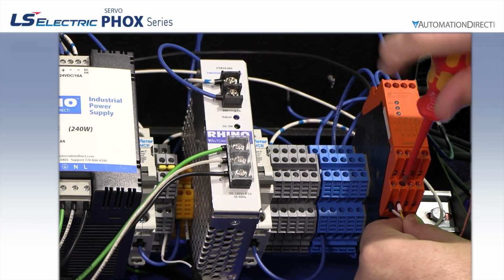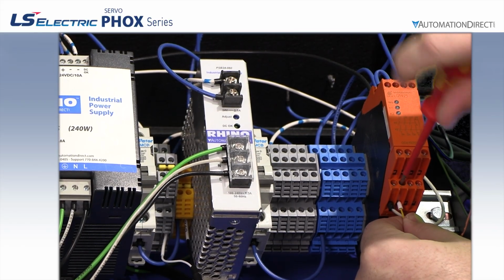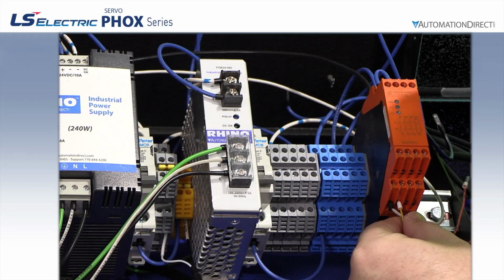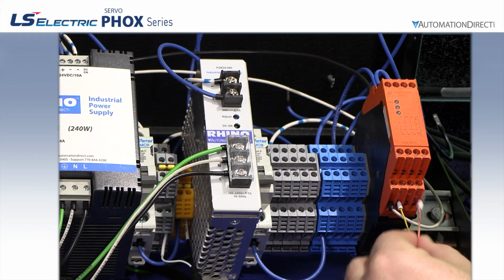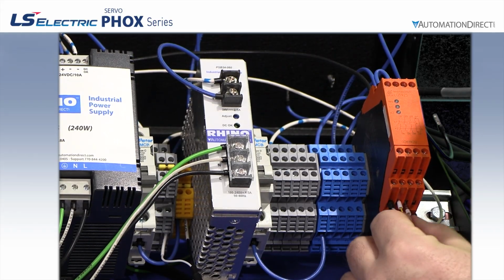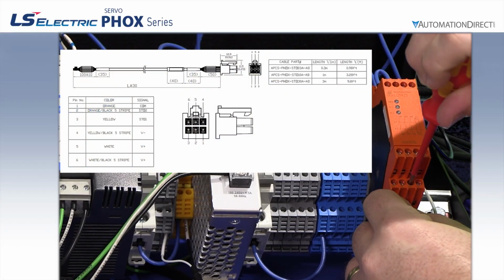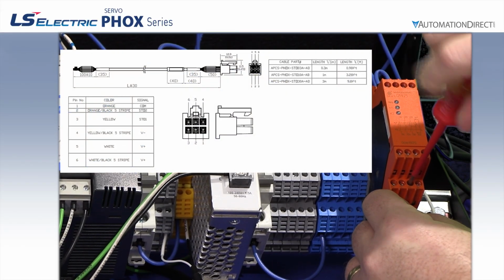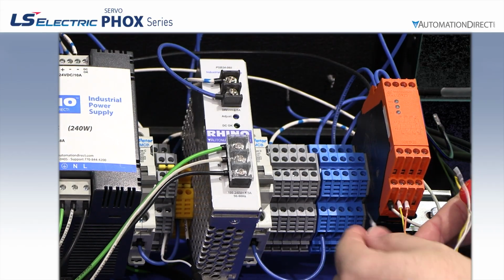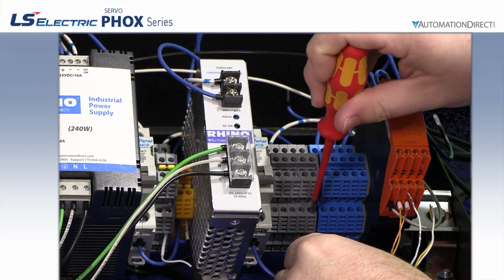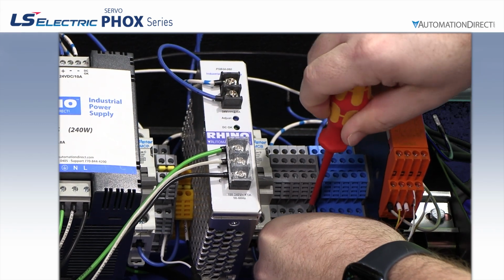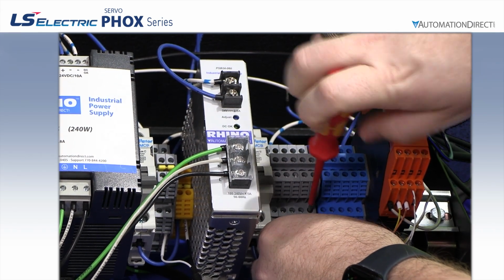Beware of the wire labels. They appear to be heat shrink tubing, but they are not. If you must cut the small wire tie holding them together, ensure you don't allow those labels to fall off the cable. If you do, the 2-dimensional drawing available from AutomationDirect.com has the wire colors and pinouts on it. Finally, connect the COM wire to the common of the power supply you are using for the 2 STO circuits. In our case, that is our control power supply.